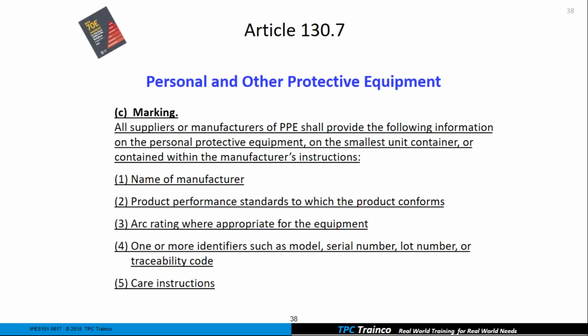Marking on my personal protective equipment. So everybody that supplies or manufactures this PPE has to provide us with some information, and somewhere it's got to be on there who actually manufactured it. So the name of the manufacturer, the product standard that it conforms to, the arc rating. So we're going to have to know how many calories per centimeter squared that clothing is.